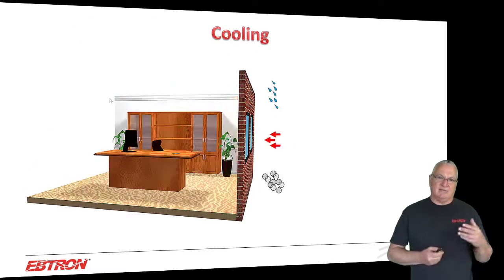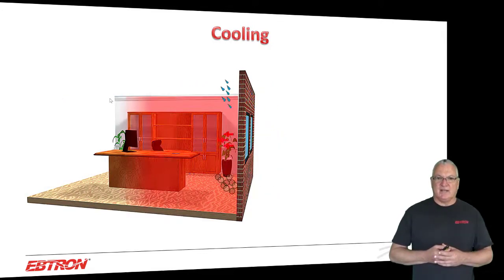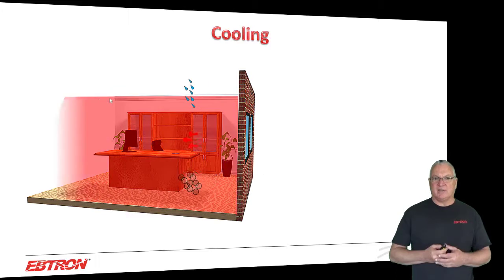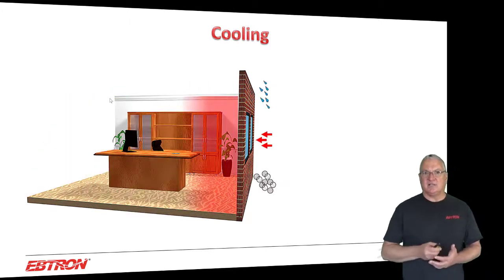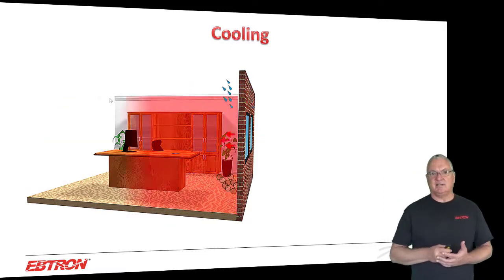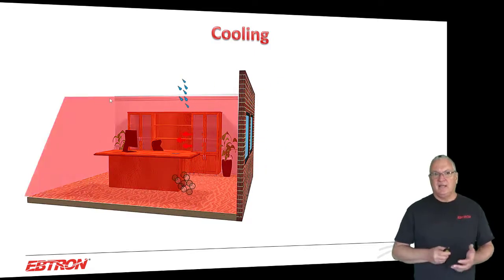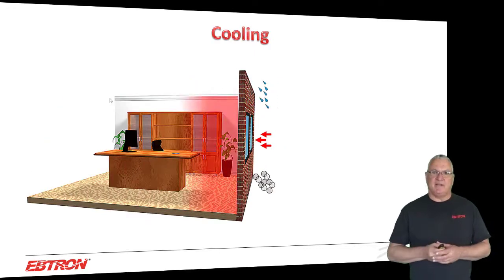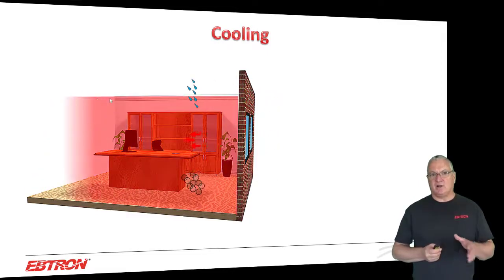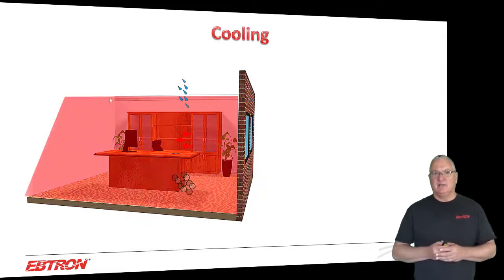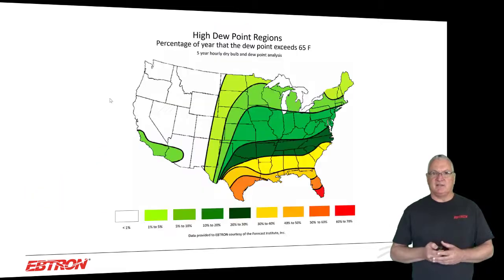And the reason for that is, let's say that we're cooling. What we're doing when we're cooling, if we're negative, is we're basically transporting three things. We're transporting untreated outdoor air, unfiltered, in terms of dirt, dust, pollen, whatever's in the outdoor air, into this space. Also, we have perimeter temperature control problems from heat. And in moist climates, we have that additional problem of moisture in the outdoor air being transported across the building envelope or into the building without ever crossing over a coil. And that's why it's so serious from an IAQ perspective.